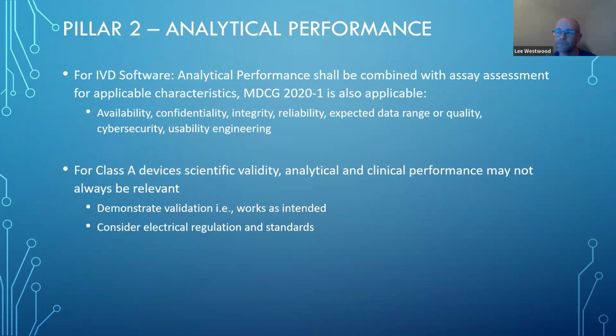Now, for Class A, scientific validity, analytical, and clinical performance might not always be relevant. For example, if you have a very low risk accessory with no critical features or functions, or you have an analyzer, scientific validity and analytical performance may be difficult to generate. But you still must generate performance evaluation, but focus it on a demonstration that the device works as you intend. So like a functional validation.